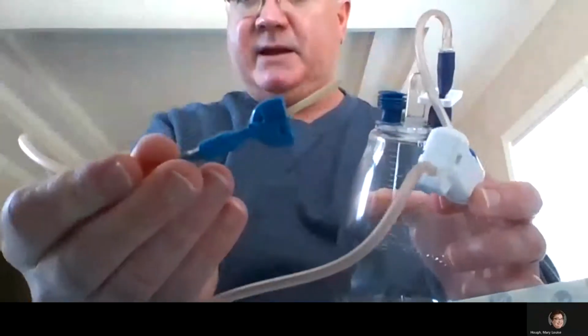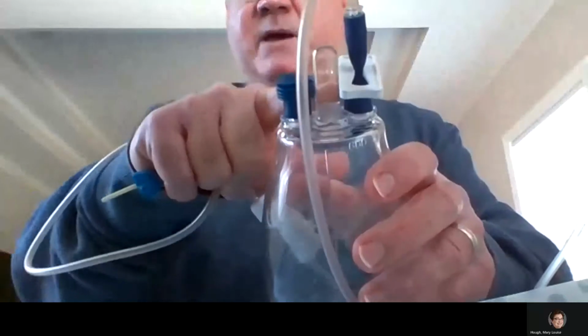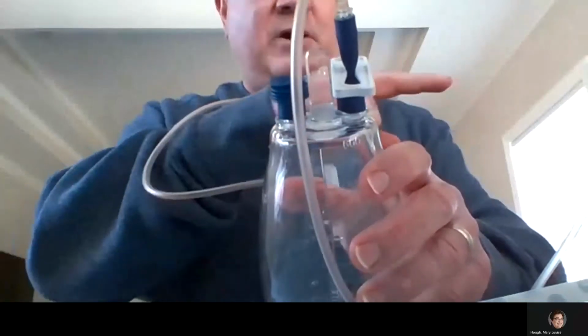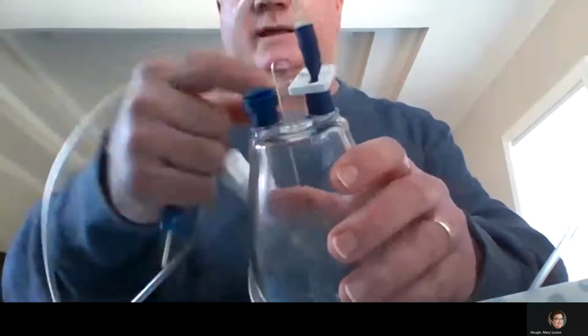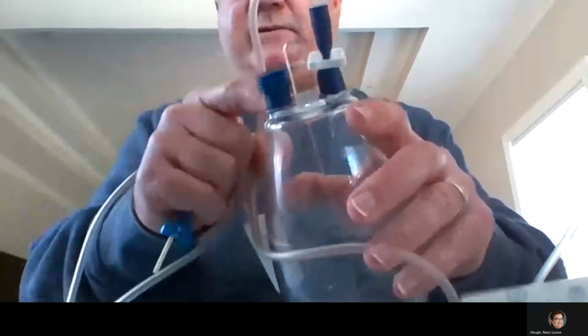So as I mentioned, though, we're all about options. So we also have a 500 milliliter bottle. Don't know if you will use these, but if you ever do, nothing is different from the 1 liter except for the size. It is the same connection at the end. It's the same push button. The only difference here is the middle tab. While we can puncture the foil seal on the 1 liter and get to that fluid, this one is self-enclosed. There's just not enough room. So this tab in the middle will not break off. So once you drain, this just gets double bagged, thrown away. You cannot get into the fluid here.